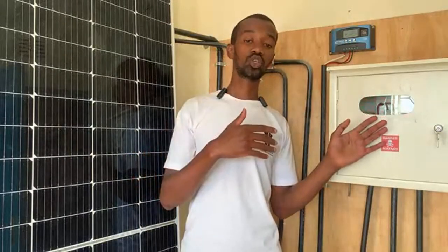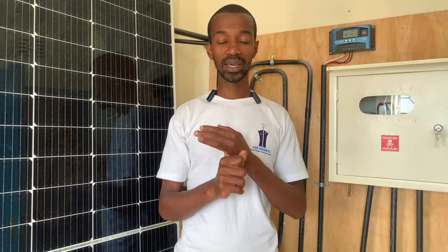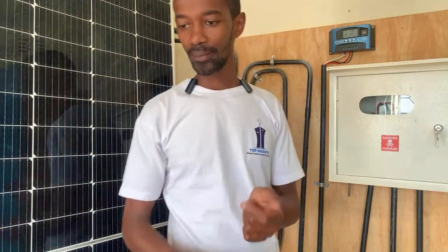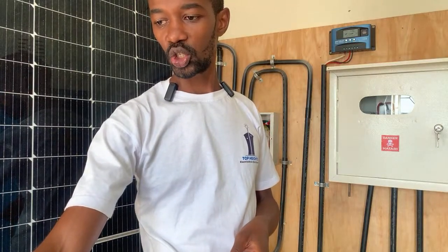So when we are talking about a connection for the heating circuits, we must ensure that from start to end, from the connection at the meter box all the way to where these heating appliances terminate, the cable size matters, the connection matters, and the gadgets you connect there matter a lot. They must be of quality material or make, and connected tightly, so that you have a perfect path for the flow of current. Remember, if the flow of current is compromised, then it will have an issue.